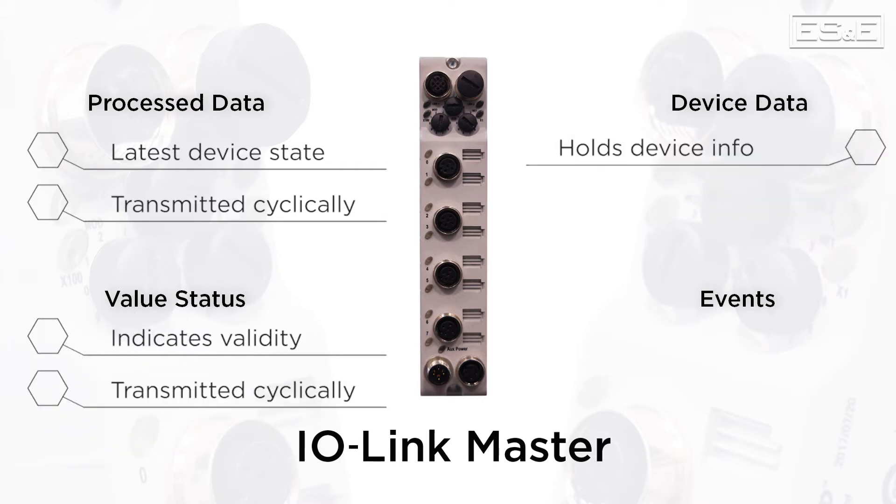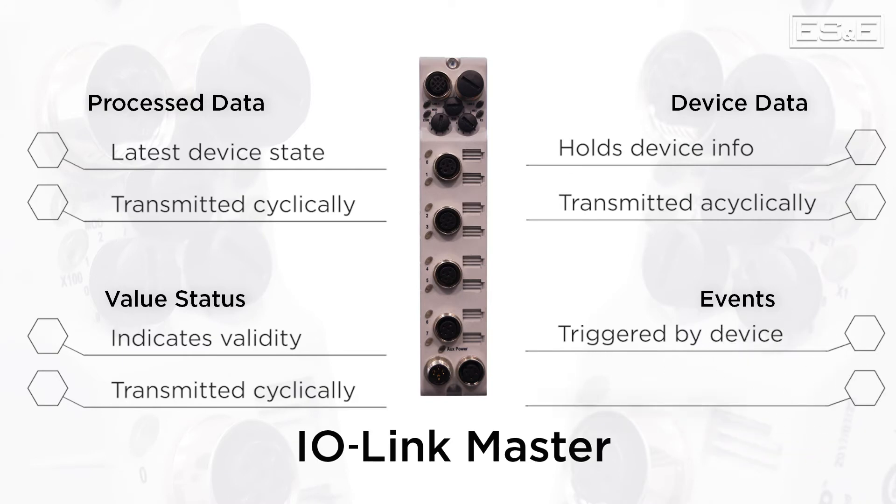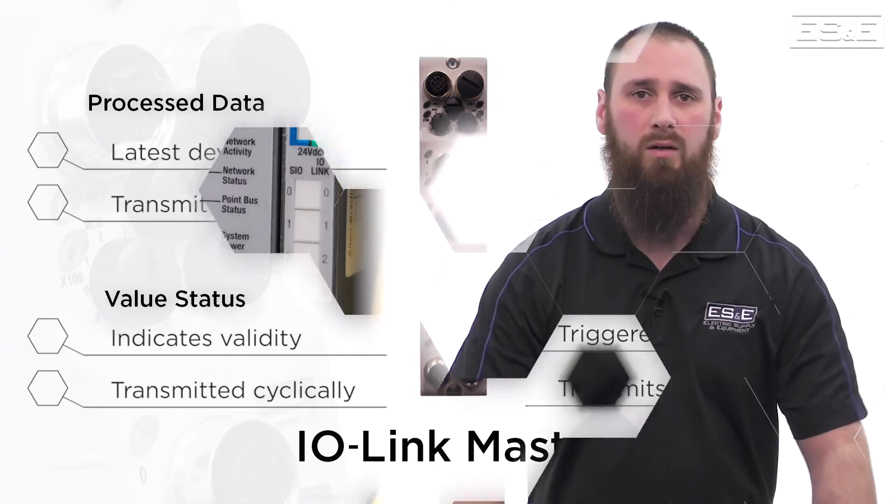The device data holds detailed information about a device, such as a serial number or revision. It also holds more advanced information, such as device parameters or diagnostic information. Device data is sent acyclically at the request of the IO-Link Master. Events are triggered by the device and are sent to the IO-Link Master as an error or warning message.